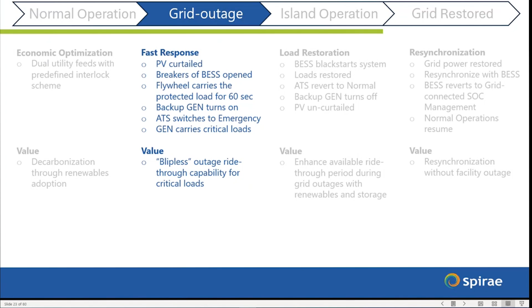Let's dive into the process of load restoration during island operation. Given the flow battery's grid forming capabilities, the system will utilize one battery unit to initiate the black start. You will observe this battery becoming the system's master, prompting the ATS to revert to normal operations and the backup generator to shut down. During this phase, load will gradually be restored and PV output will resume.